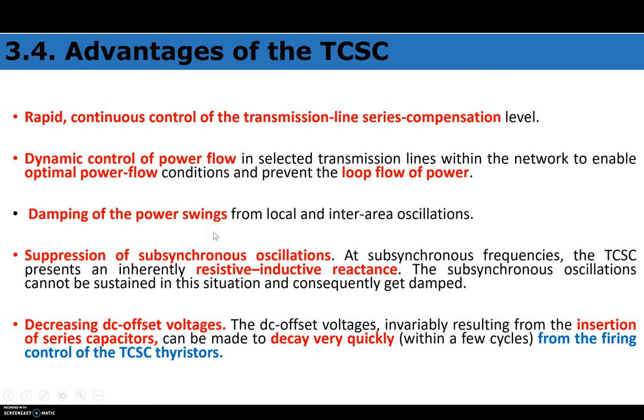Damping of power swings is another benefit. Power swings are damped as the additional controllable reactance provides damping actions for both local and inter-area oscillations. TCSC also suppresses sub-synchronous oscillations, because at sub-synchronous frequency the TCSC presents an inherently resistive-inductive reactance. Since the inductor is connected in parallel with the capacitance and controlled continuously by thyristor action, sub-synchronous oscillations are damped by this inductive reactance and consequently cannot be sustained.